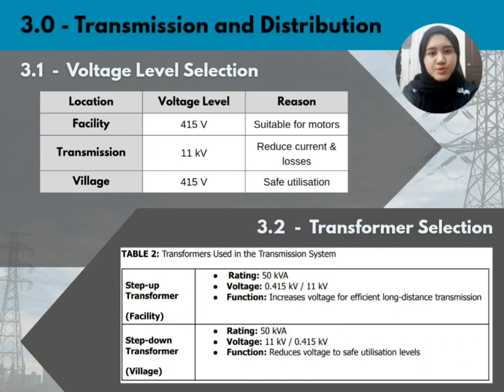And we've selected two transformers for this task. A step-up transformer at the facility increases the voltage to reduce current and heat loss during transmission. And at the receiving end, a step-down transformer brings it back to 415 volts for safe use by the villagers.